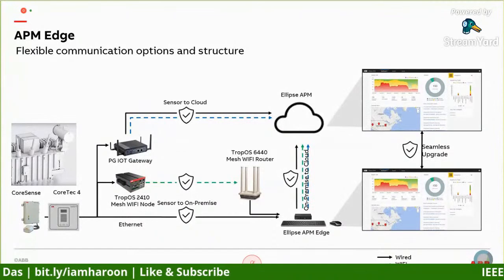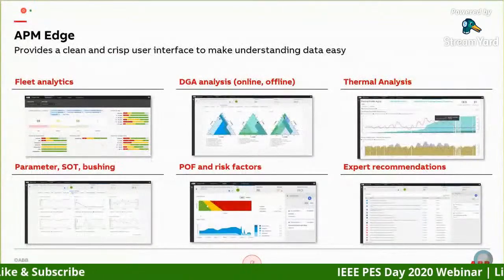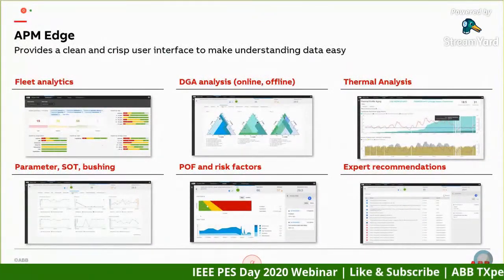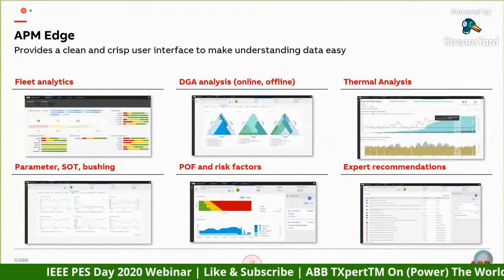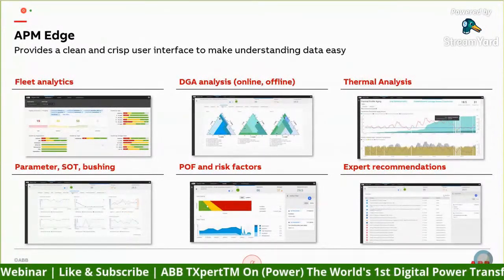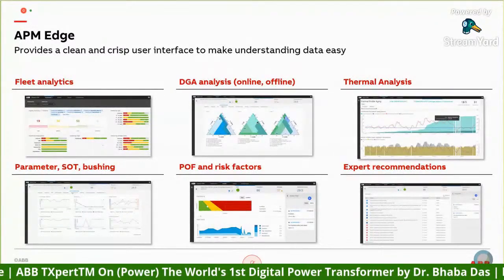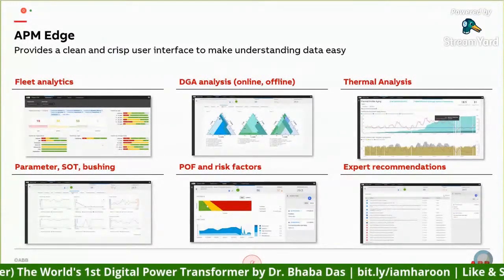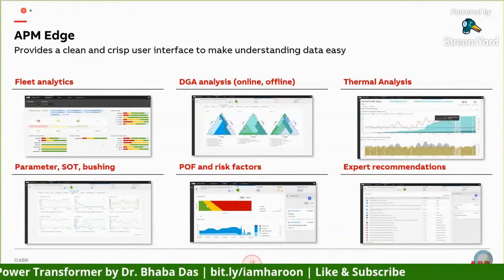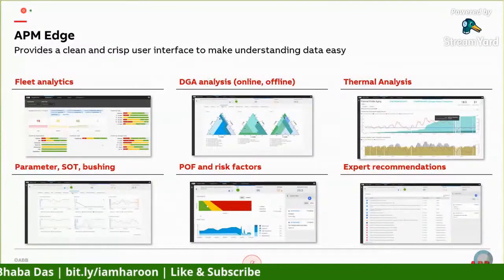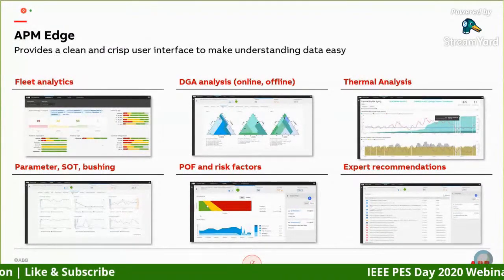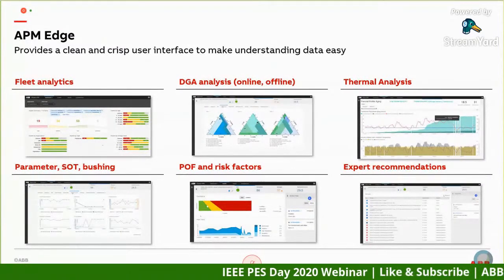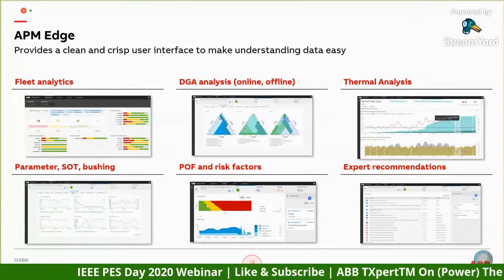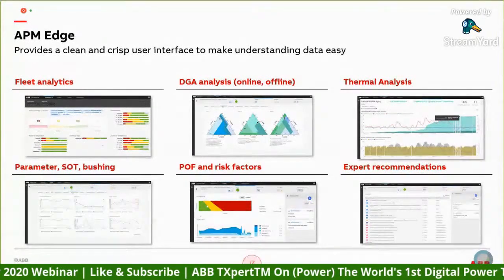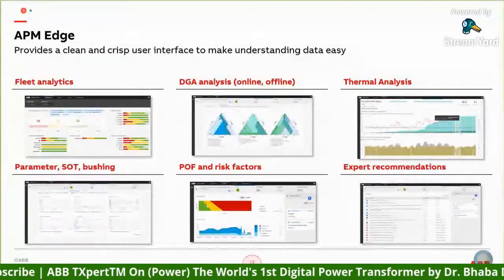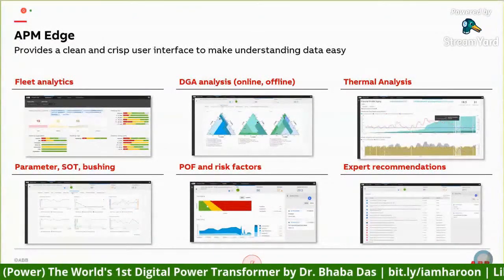What APM will bring to you is fleet level analytics, DGA analysis, offline, online. For online, we take care of 13 different manufacturers apart from ABB. We have algorithms developed for each and every one of those 13 different manufacturers. You can have ABB's Core Sense, you can have Transfix, Calisto, Hydran. We have algorithms for each one of that.